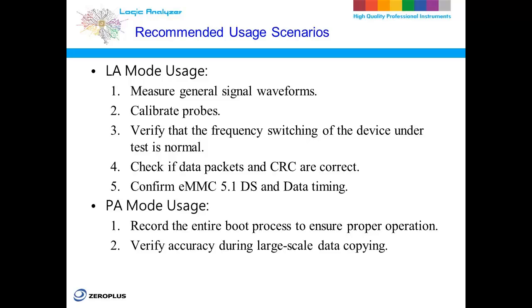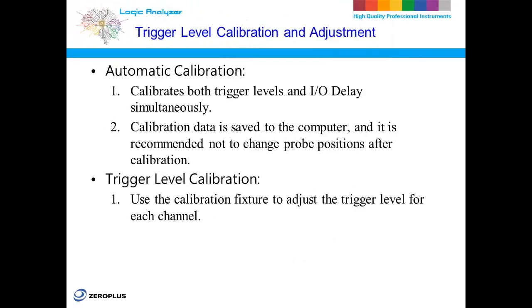By choosing the right mode for your measurement, you can pinpoint issues more accurately, improve measurement precision, and enhance the overall efficiency of the testing process. When using Bus Expert 2 for measurements, it's crucial to perform trigger level calibration and adjustments to ensure accuracy and consistency in your results. Not only does this improve measurement precision, but it also ensures that the data is not skewed by any irregularities in the trigger signal.